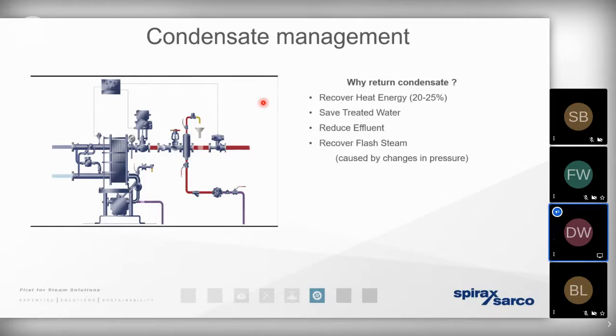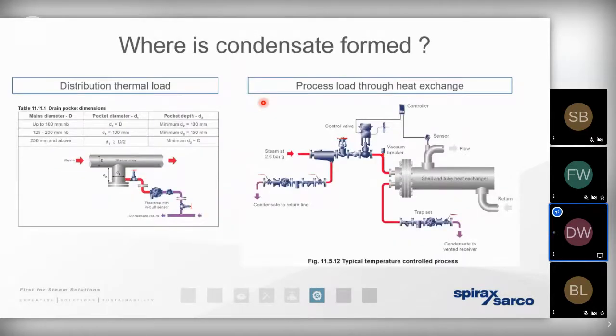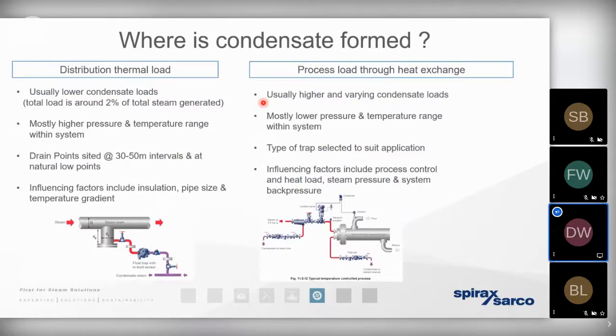And that's going to help us to bring the boiler back up to the point where it can generate steam rapidly and efficiently. So I want to move forward and look at the different areas where condensate is actually formed or produced. So condensate exists wherever steam gives up its heat energy, wherever there's a heat loss. So first of all, that can be in the distribution pipework itself, and it can be at the process. They're the two different areas where we're going to get condensate.